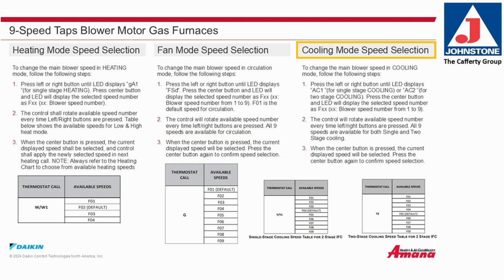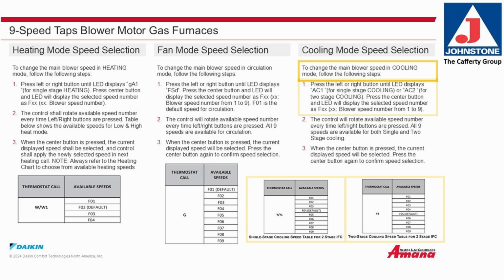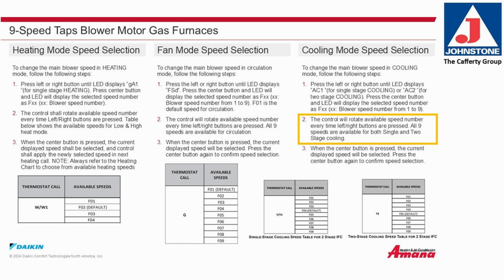Cooling mode speed selection. To change the main blower speed in cooling mode, follow these steps. Press the left or right buttons until the LED displays AC1 for single-stage cooling or AC2 for two-stage cooling. Press the center button and the LED will display the selected speed number as F and 2 digits, 01 through 09. The control will rotate available speed number every time the left and right buttons are pressed. All 9 speeds are available for both single and two-stage cooling. When the center button is pressed, the current displayed number will be selected. Press the center button again to confirm that speed selection.